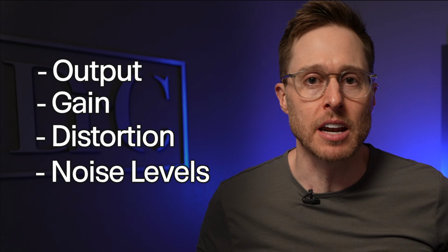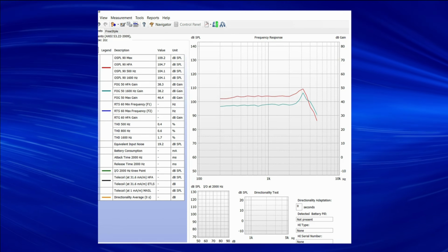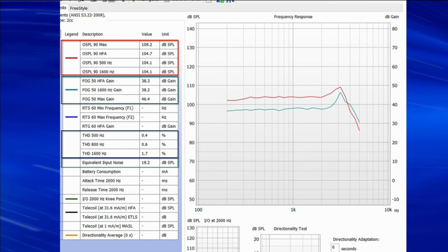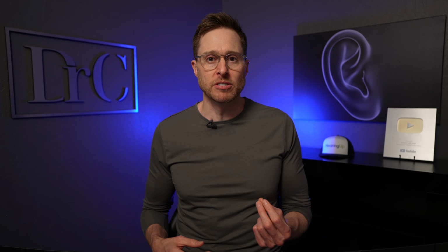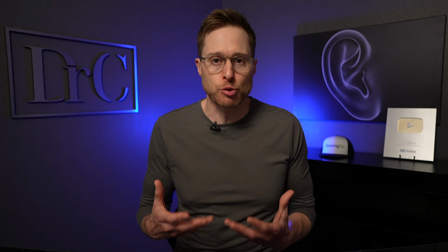This particular test measures things like output, gain, distortion, and noise levels inside of your hearing aids. All of these diagnostic measures have to be within the tolerance ranges for that particular hearing aid, otherwise the hearing aids fail diagnostics. And this ultimately reduces the performance of your hearing aids. And the crazy thing is, nobody is able to identify if your hearing aids are meeting manufacturer specifications unless you run them through the test box.